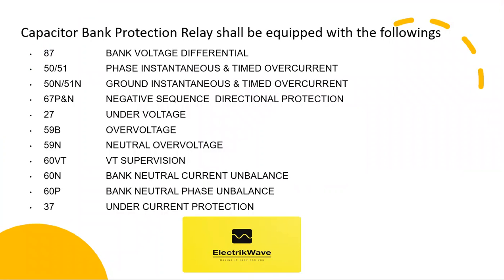Capacitor bank protection relay shall be equipped with the following: 87 bank voltage differential; 50, 51 phase instantaneous and timed over current; 50N, 51N ground instantaneous and timed over current; 67P and N negative sequence directional protection.